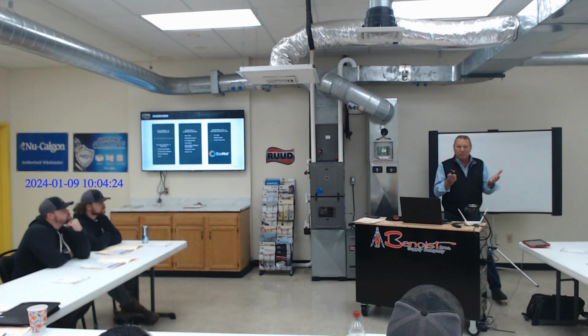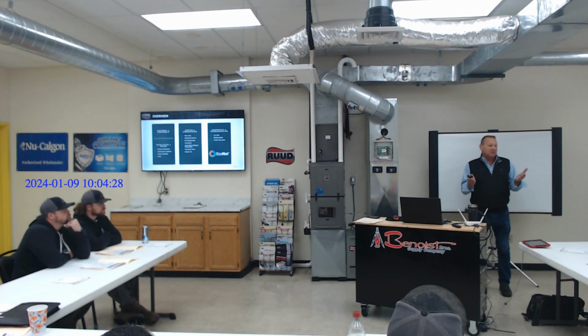You can calculate if you get a 5-ton outdoor unit non-communicating, let's just go 69% to be safe. What's 69% of 60,000? It'd be like 1,400 CFM. You're somewhere in there. So your smallest zone is going to need to be able to handle that CFM for a 5-ton, okay? And when we calculate CFM of these duct systems, I don't care if my trunk size is 12 by 24 going in one direction. How many 6-inch runs do I have coming off of that? If I got 7 6-inch runs coming off of 12 by 24, it's the smallest part of the zone, right? I can't shove 1,400 CFM through 6-inch runs.